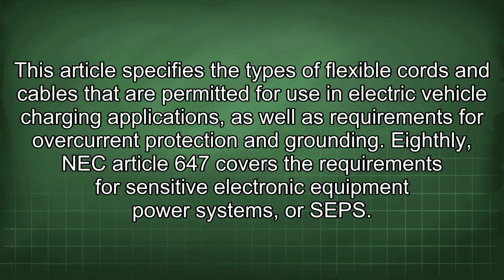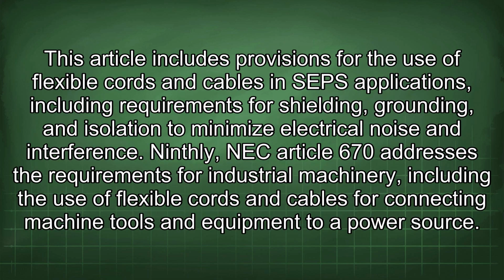Eighthly, NEC Article 647 covers the requirements for sensitive electronic equipment power systems, or SEPS. This article includes provisions for the use of flexible cords and cables in SEPS applications, including requirements for shielding, grounding, and isolation to minimize electrical noise and interference.